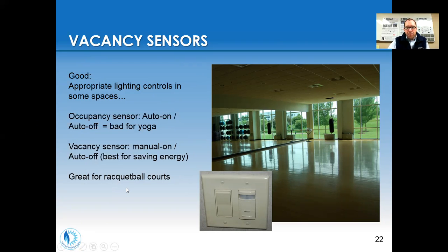These are also great for racquetball courts. Having an occupancy sensor in a racquetball court, where the lights would otherwise just be on during the entire day of operation, is useful since you might only have racquetball for a few hours of that. One of the big hurdles was that a lot of racquetball courts had metal halide lights - really bright - and those took a long time to turn back on once you turned them off.